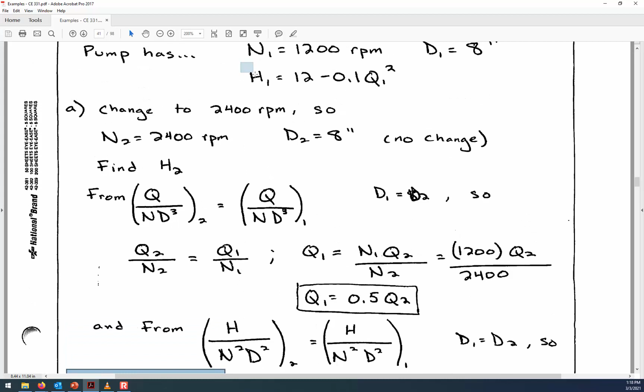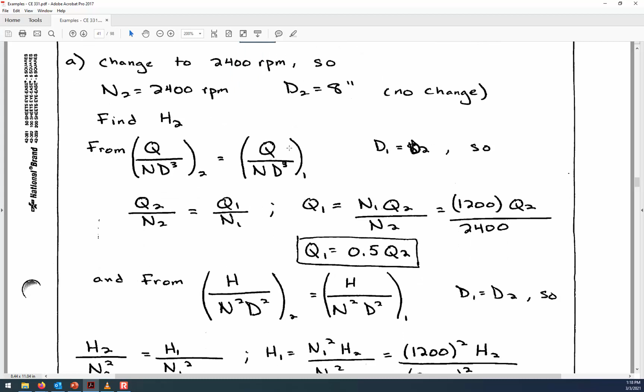I want to substitute something in here into the original curve, something new so that I can get H2. So how does H2 and H1 relate? Okay, so H1 is a quarter of H2. When it spins twice as fast, you're going to get 4 times as much pump head.